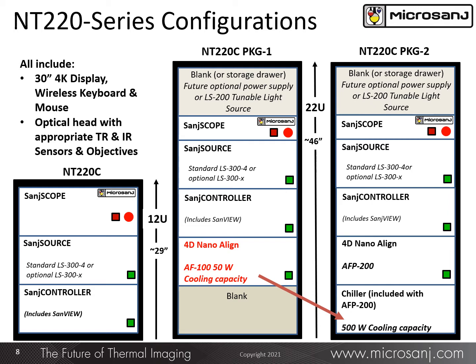In package 2, we have a piezo calibration tool with a larger working stage, 125 millimeters by 125 millimeters, with a 20 to 150 degree temperature range and a 500 watt cooling capacity. The chiller fills the 4U slot at the bottom of the rack, but there is still a 4U slot for an optional accessory at the top.